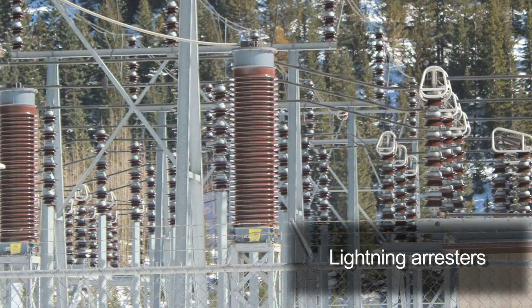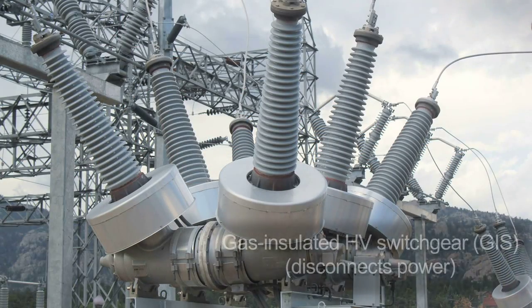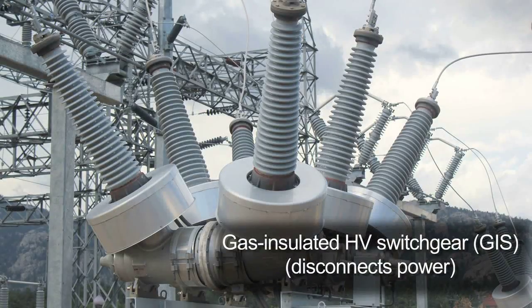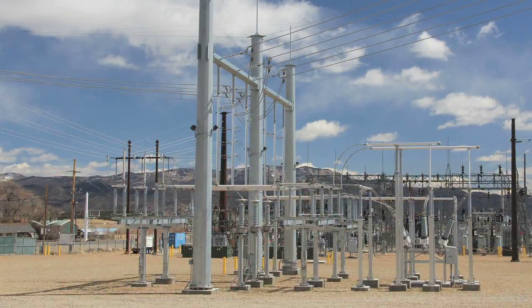Each device has both power circuit breakers to protect it and to interrupt a fault on either a transformer or a line, and then the protective relaying that goes along with circuit interruption devices to decide whether this is a temporary or a sustained fault. For instance, in a power transformer, any fault is a lockout, or treated as a sustained fault.